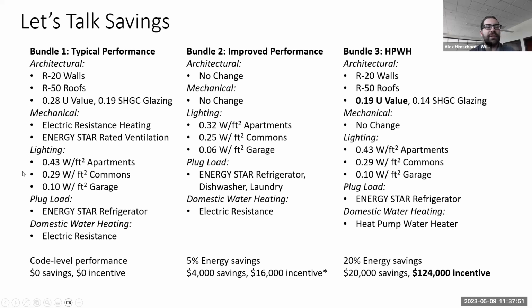On the lighting side, we're sticking to that 30%. I've translated, rather than percentages, the most common watts per square foot for these spaces: 0.43 apartments, 0.29 commons, 0.10 garage. Minimal influence on plug load, but you're almost certainly putting in a refrigerator, and if so, it's almost certainly Energy Star rated, so we're putting that in there.